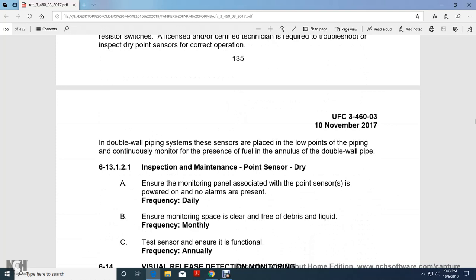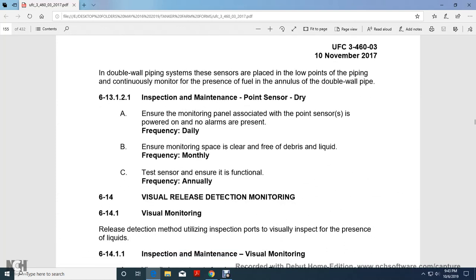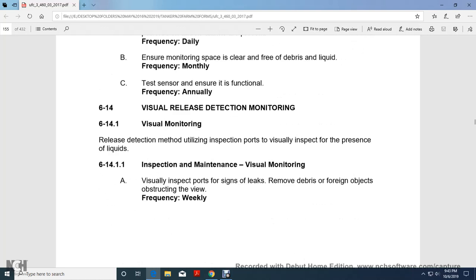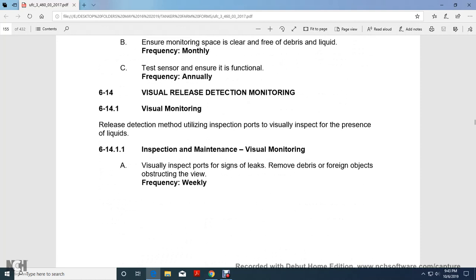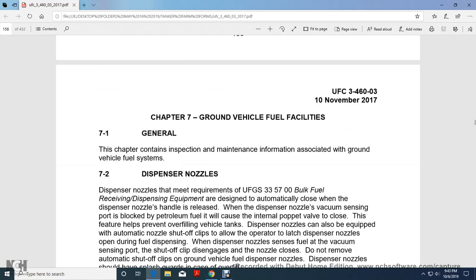For double wall piping, these sensors are placed in low points of the piping for continuous monitoring of fuel within the annulus of the double wall piping. Inspection maintenance of dry point sensors: ensure the monitoring panel associated with the point sensor is powered on and no alarms are present, daily. Ensure the monitoring space is clear and free of debris, monthly, and test the sensor to ensure functionality, annually. Visual release detection monitoring is a release detection method utilizing an inspection port for visual inspection for the presence of liquid. Inspection maintenance, visual monitoring: visually inspect the port for signs of leaks, and remove debris, foreign objects and obstructions from the view, weekly. Chapter 7, Ground Vehicle Fuel Facilities.